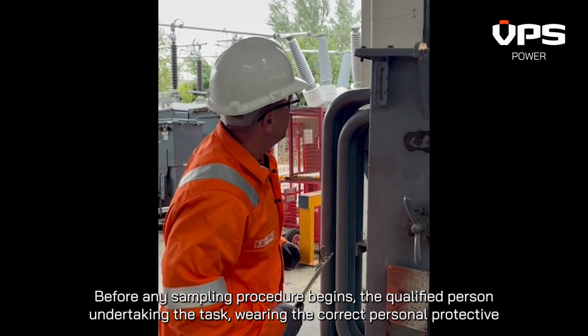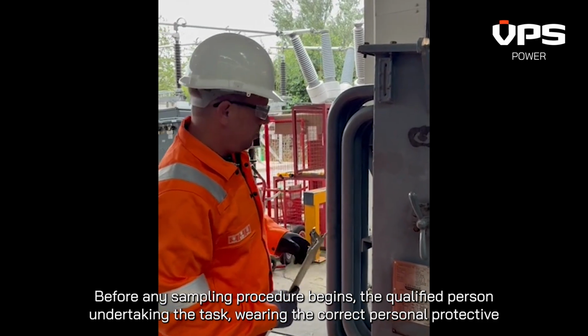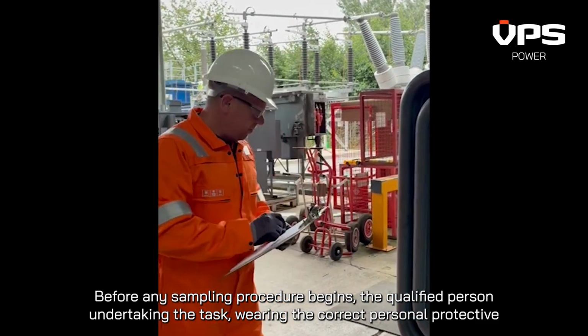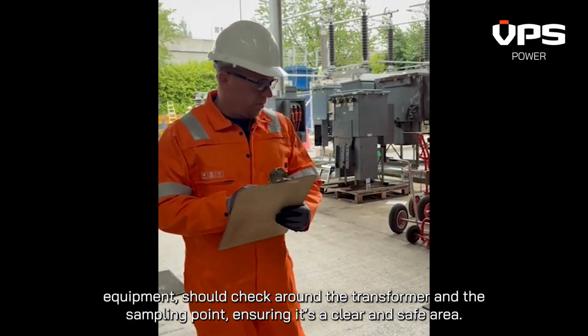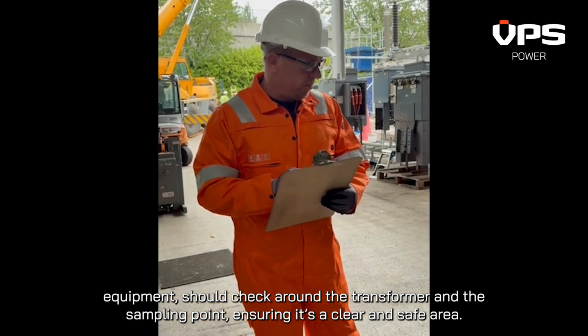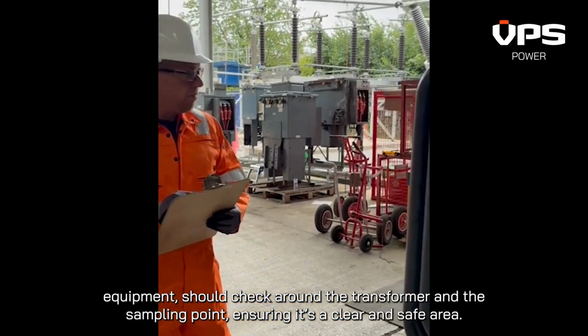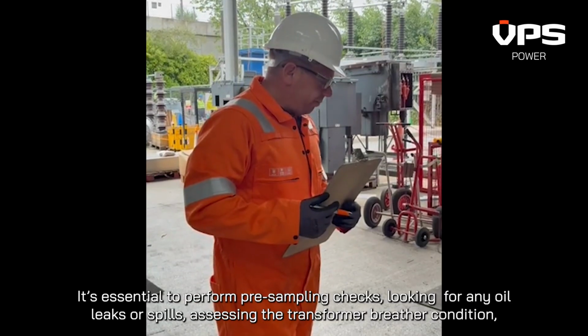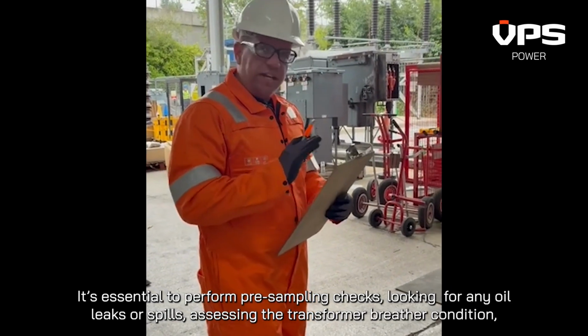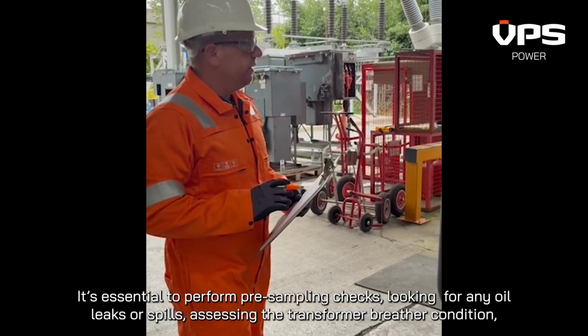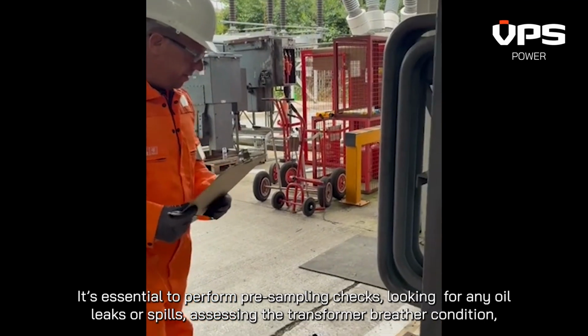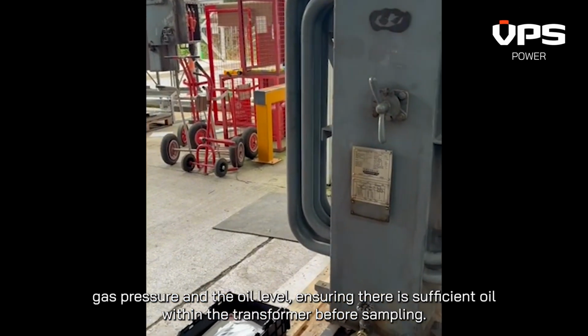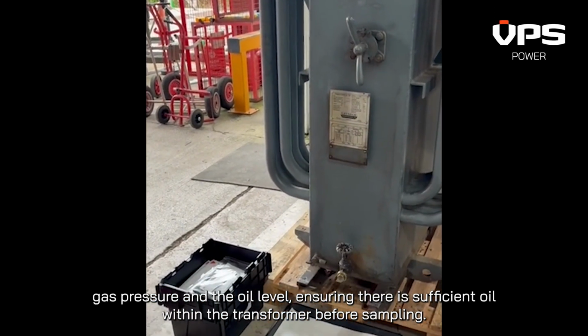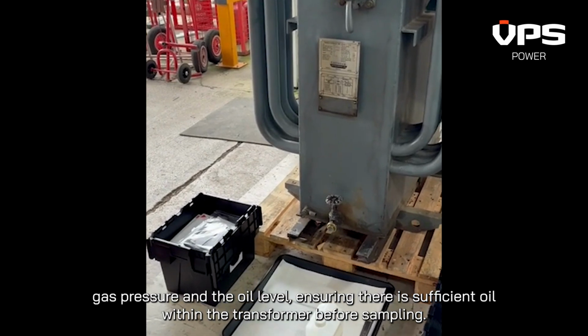Before any sampling procedure begins, the qualified person undertaking the task, wearing the correct personal protective equipment, should check around the transformer and the sampling point, ensuring it's a clear and safe area. It's essential to perform pre-sampling checks, looking for any oil leaks or spills, assessing the transformer breather condition, gas pressure and the oil level, ensuring there is sufficient oil within the transformer before sampling.